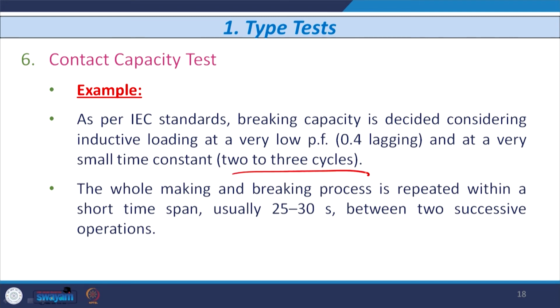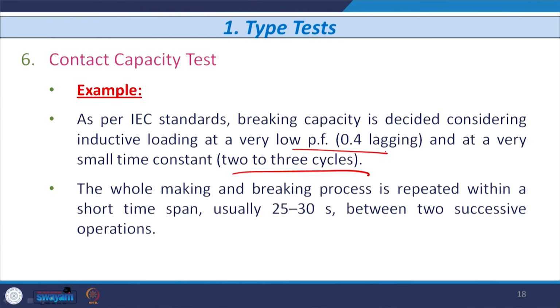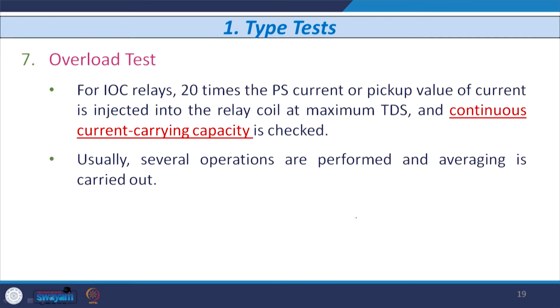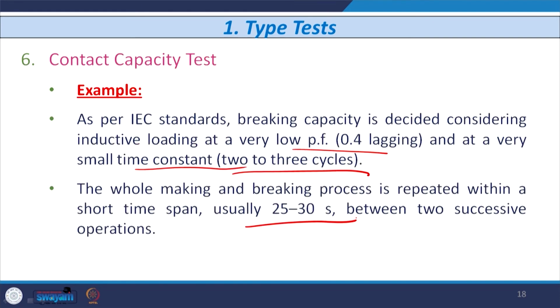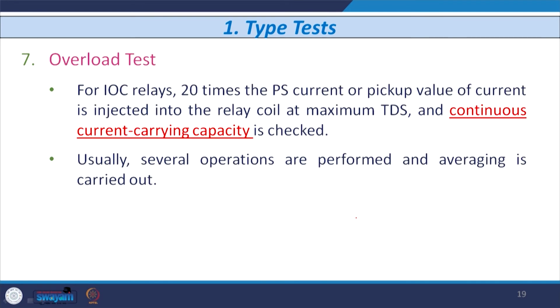In this standard they have defined what conditions you need to create when you carry out the contact capacity test. The power factor should be very low and the time constant should also be very low, in the first 2 to 3 cycles immediately after that point, which is very important. The whole making and breaking process is repeated within a short time span, usually 25 to 30 seconds between two successive operations. This is how the contact capacity test is to be performed.